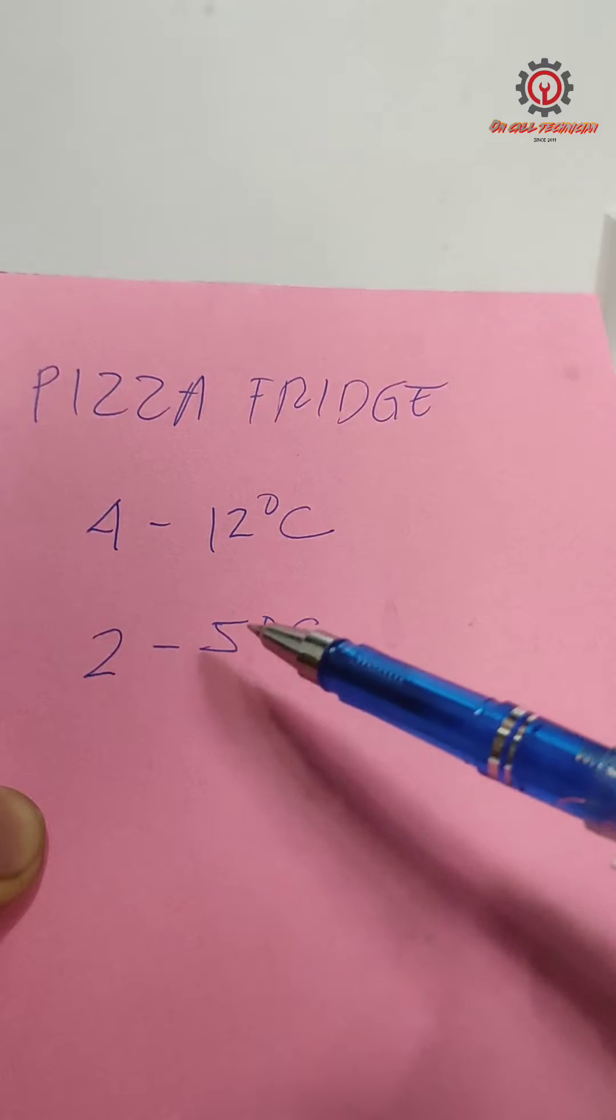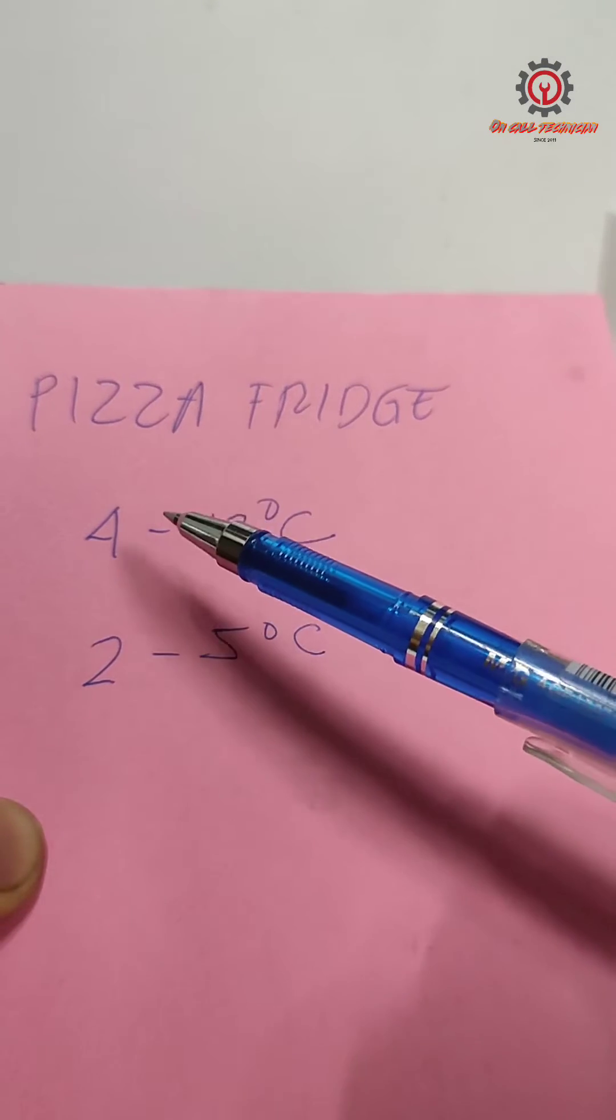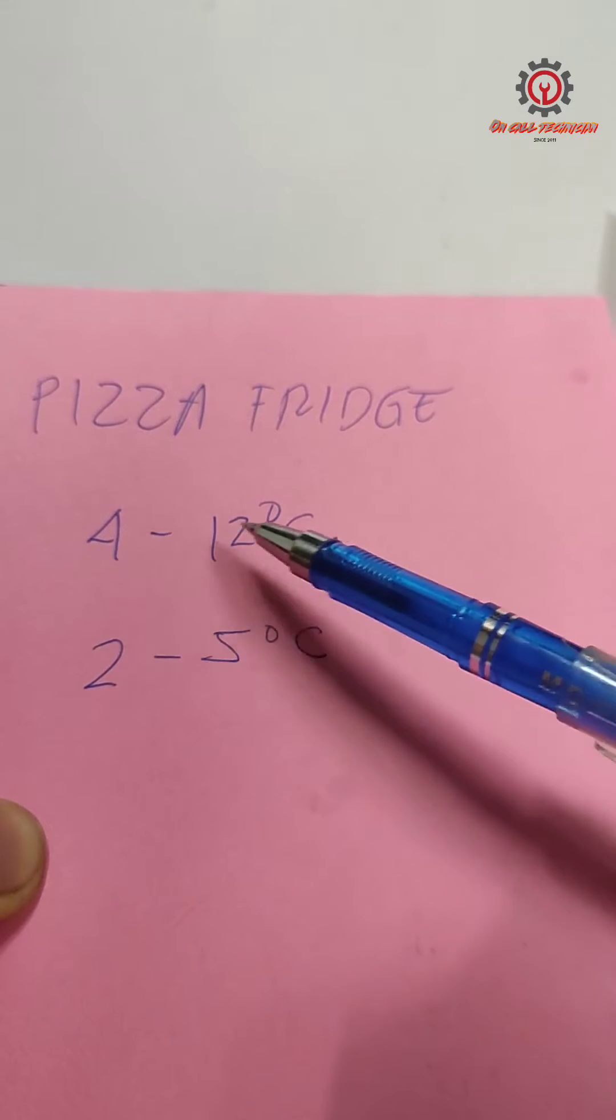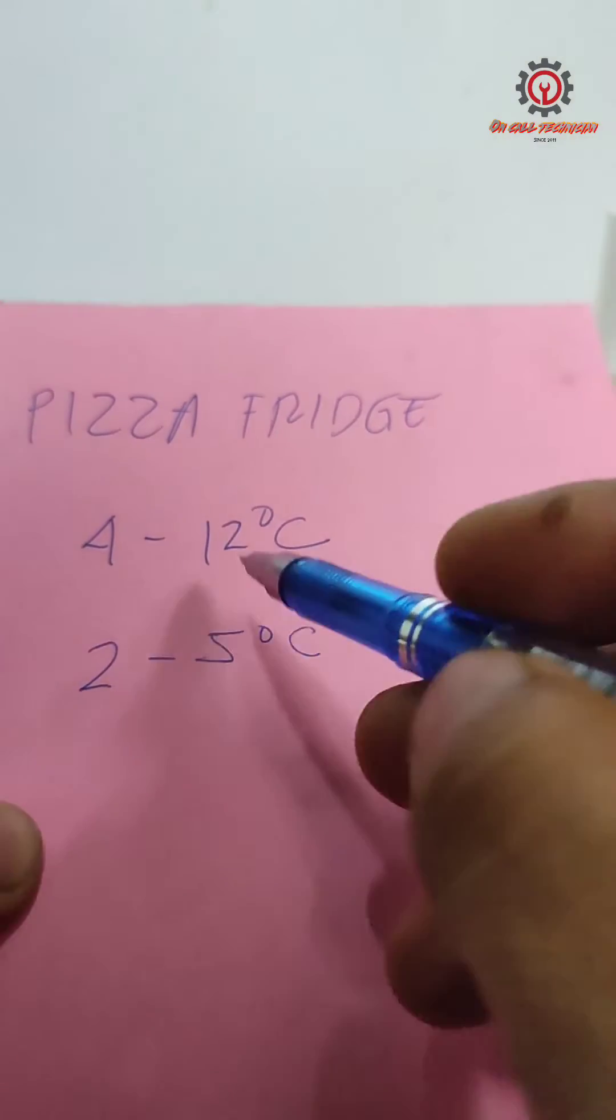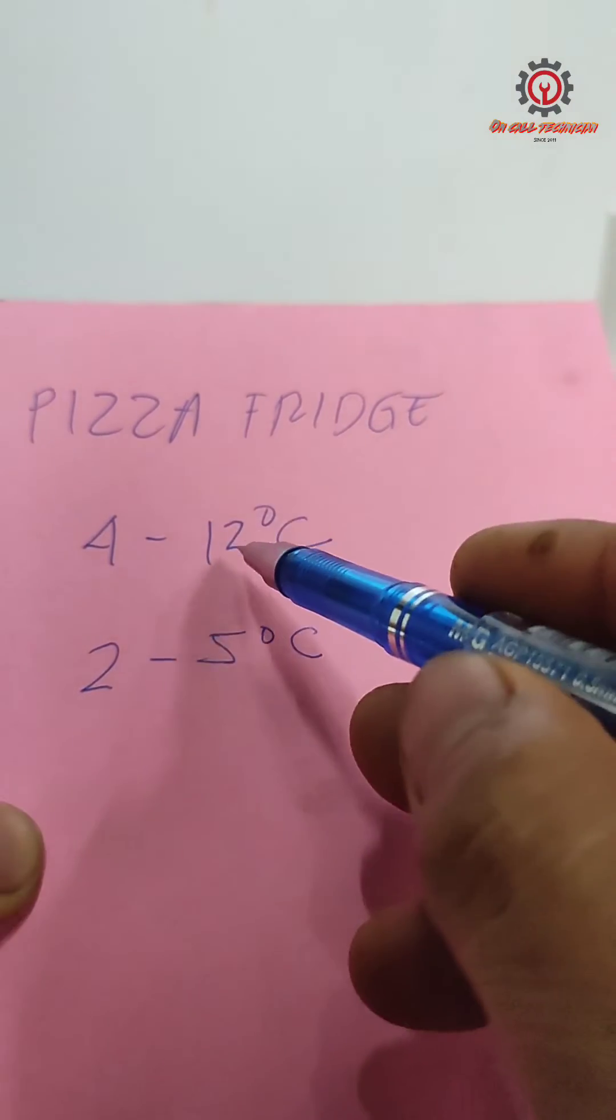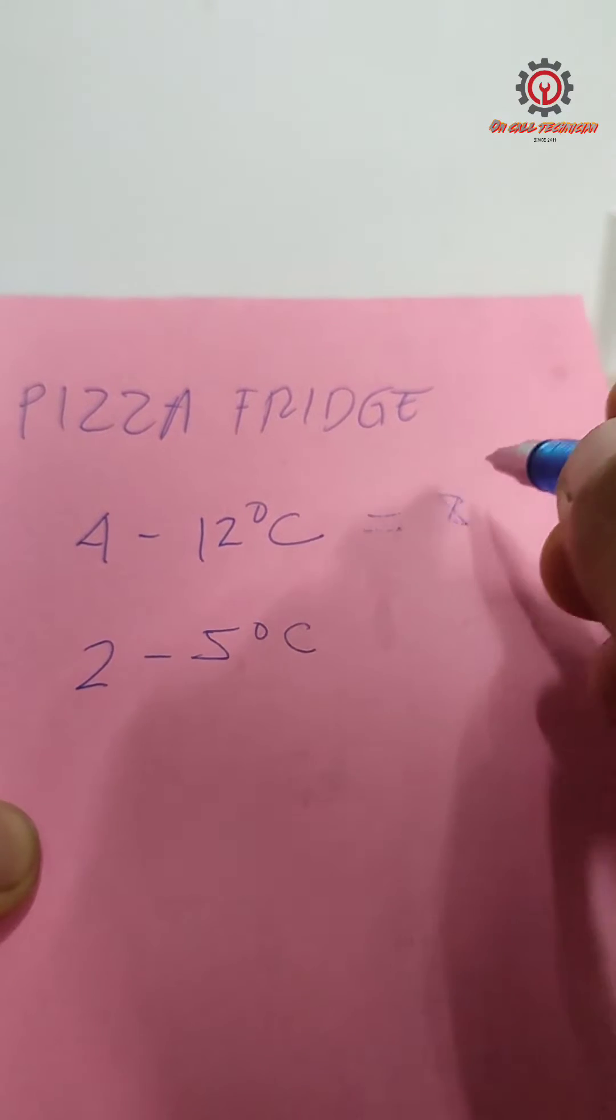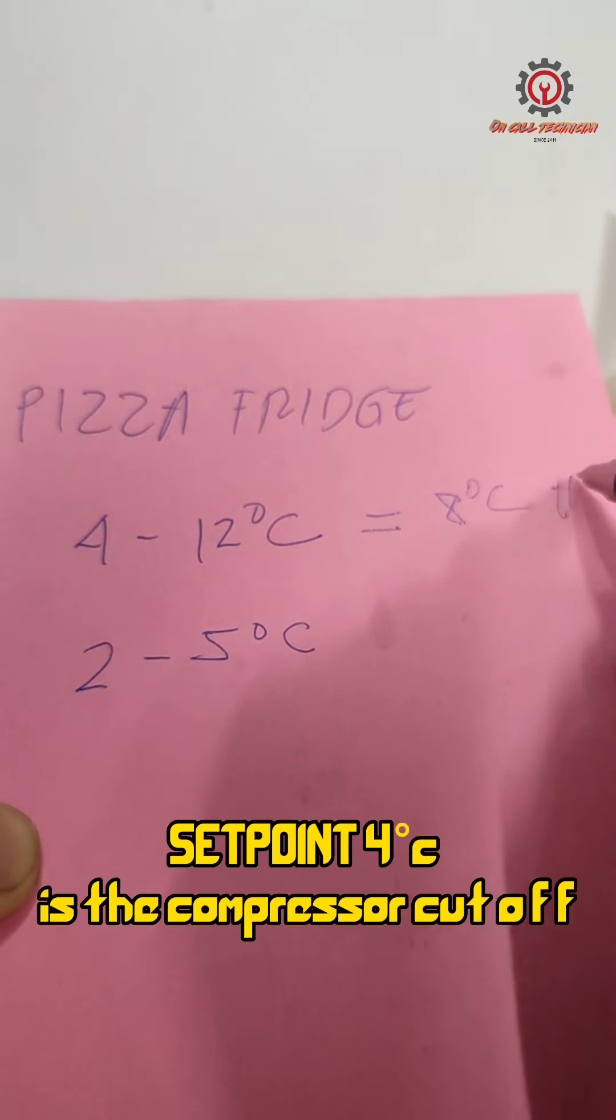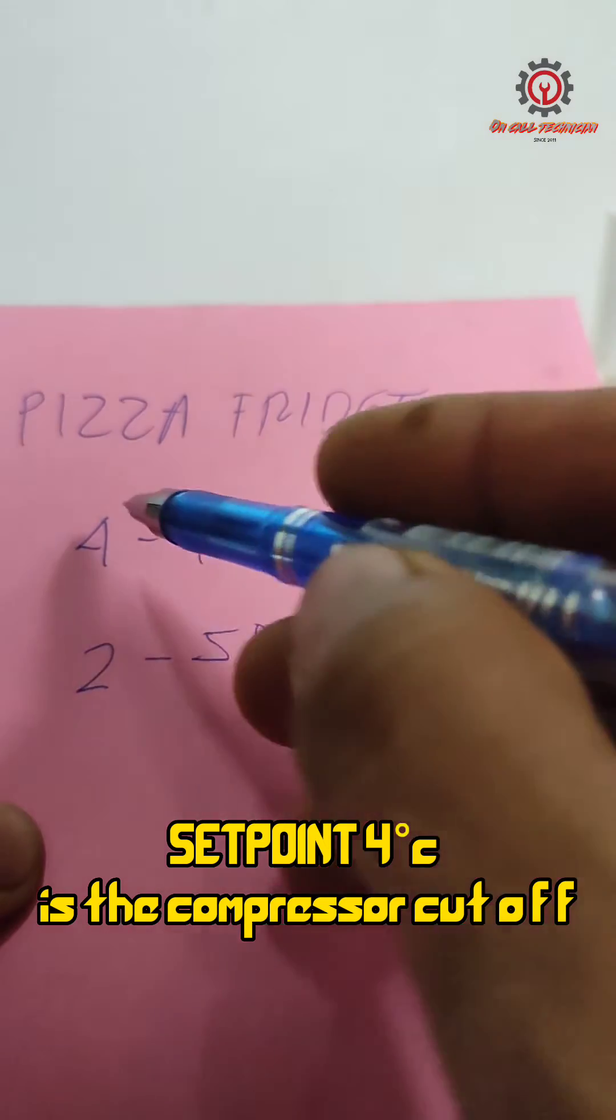Currently the stored value in his controller is 4 to 12 degrees Celsius. Now if you're going to minus this: 12 minus 4 is 8 degrees Celsius. Therefore, the 8 is the HY, the differential of the compressor.